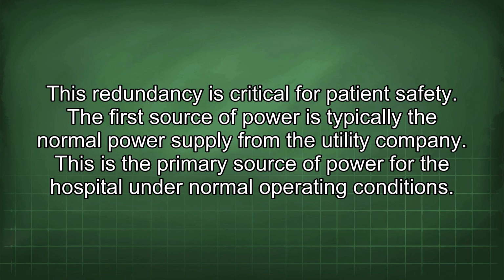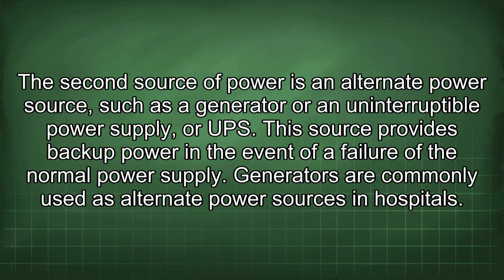The first source of power is typically the normal power supply from the utility company. This is the primary source of power for the hospital under normal operating conditions. The second source of power is an alternate power source, such as a generator or an uninterruptible power supply, or UPS. This source provides backup power in the event of a failure of the normal power supply.